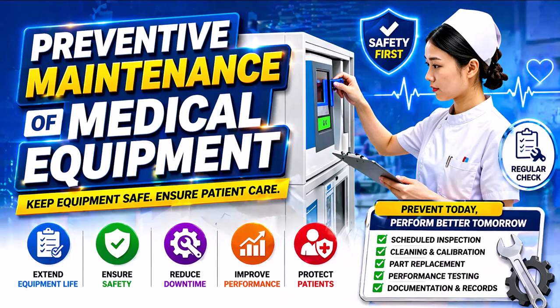A typical preventive maintenance procedure begins with a visual inspection. During this step, the technician checks the physical condition of the device, including cables, connectors, housings, and accessories. Signs of wear, damage, or contamination must be identified and addressed. Visual inspection is simple but highly effective in detecting early problems.